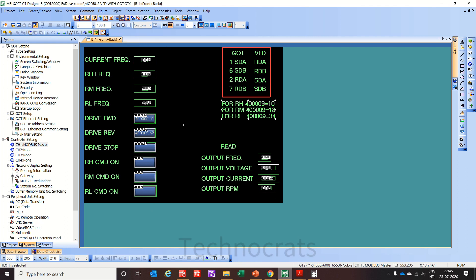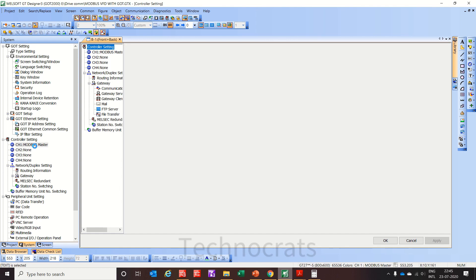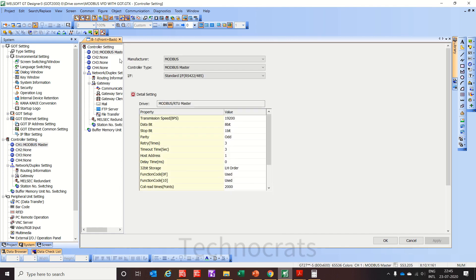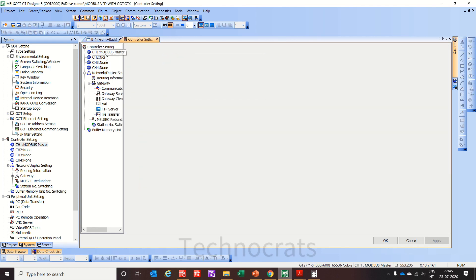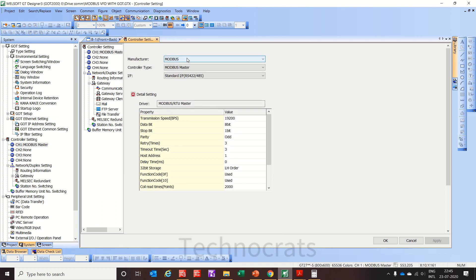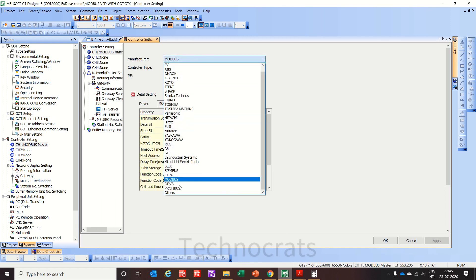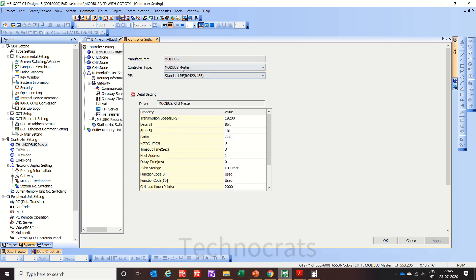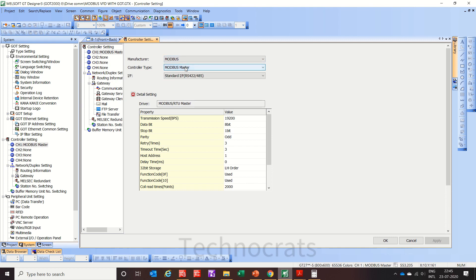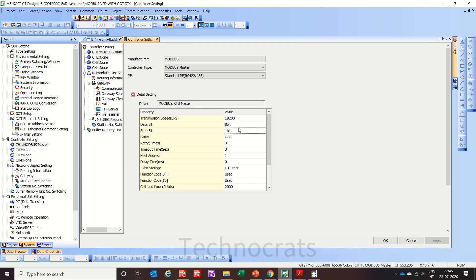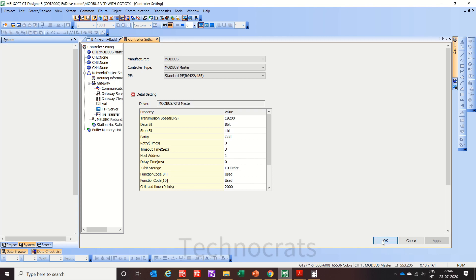First of all let me show you what settings I have done. This is channel 1, Modbus master using Modbus as manufacturer, control type as Modbus master, and my interface is RS-485. This is our setting: baud rate is 19200, data bit is 8 bit, stop bit is 1, parity is odd.